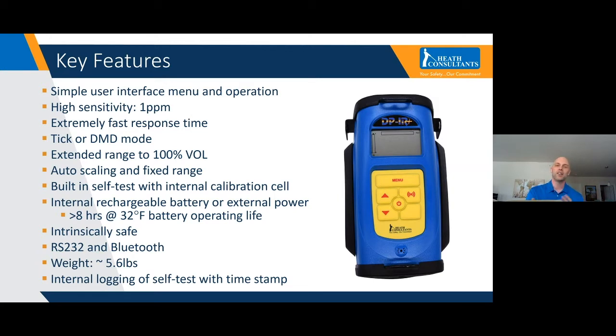The tick mode, it's kind of like it sounds. It's a constant tick tick, like a Geiger counter. As gas increases, the tick rate increases. But most likely, you're using the DMD mode on there. So the DPIR, I mentioned it goes from 1 part per million. It goes upwards to 100% volume gas and air. So it really mimics anything that a combustible gas indicator could do. So it's a versatile instrument.